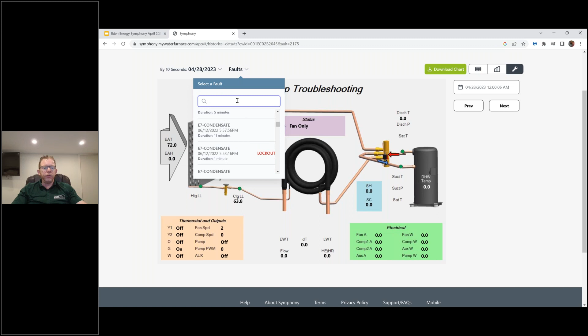So you have the options of you can just scroll down and find your fault, or you can do this. You can say, okay, I know it's a condensate fault, I'd like to find the E7 faults. And then when you pull that fault up, it's going to show that live troubleshooting form that we selected and go, okay, here is what happened when this unit was locked out. And we can now start to drill down to figure out what happened.